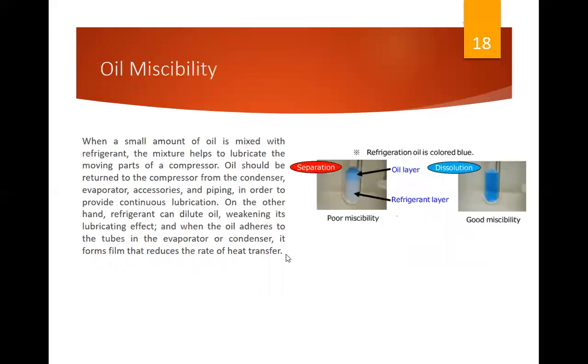Next characteristic is the oil miscibility. When a small amount of oil is mixed with refrigerant, the mixture helps to lubricate the moving parts of a compressor. Oil should be returned to the compressor from the condenser, evaporator, accessories, and piping in order to provide continuous lubrication. On the other hand, refrigerant can dilute oil, weakening its lubricating effect, and when the oil adheres to the tubes in the evaporator or condenser, it forms a film that reduces the rate of heat transfer.